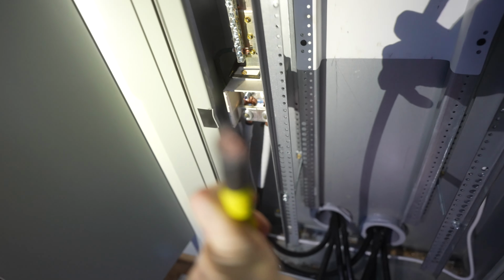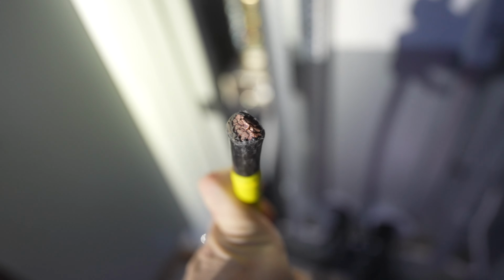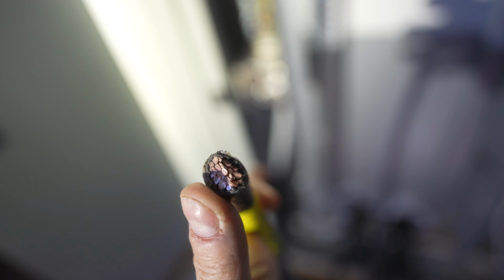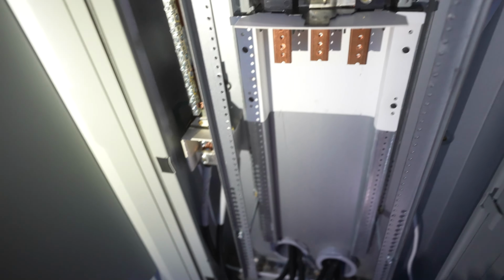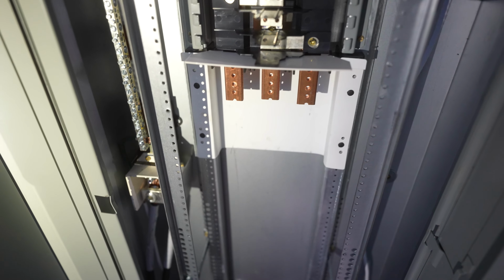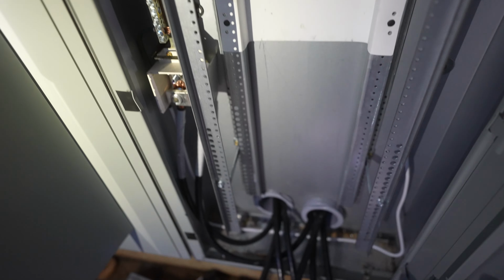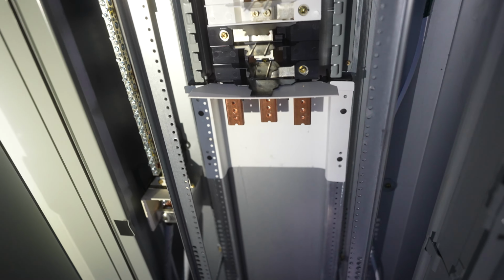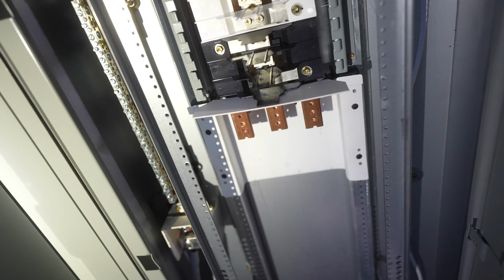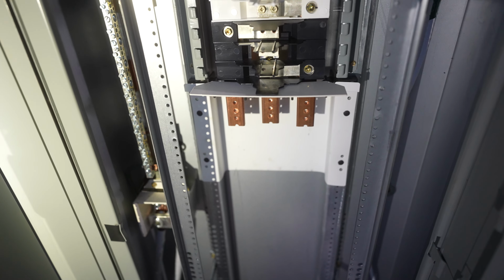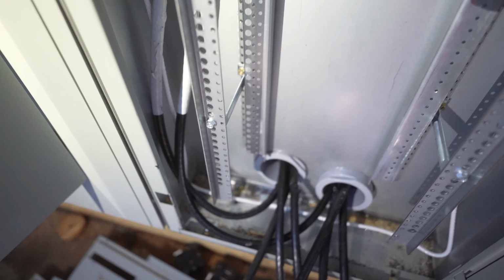It's really, really thick. Let me bend this guy over here. It's really, really thick copper. Try to focus. There we go. Really, really thick copper. So this copper is going to give us 400 amps for this panel. Now that's 400 amps at 416, which means that each leg is 240. You combine the legs and it becomes 416. So we have 240 volts coming on each leg, and that thing's at 4-aught. So that's a lot of power coming in. I think, as I recall, might be mistaken, it's about 216,000 watts, I think, is the load on each panel here.